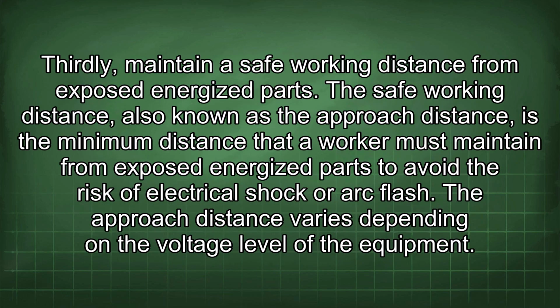Thirdly, maintain a safe working distance from exposed energized parts. The safe working distance, also known as the approach distance, is the minimum distance that a worker must maintain from exposed energized parts to avoid the risk of electrical shock or arc flash. The approach distance varies depending on the voltage level of the equipment.